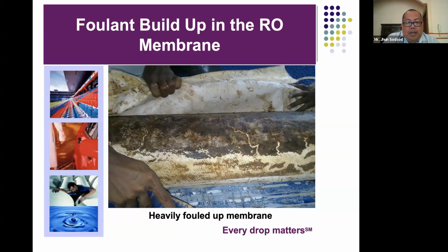So to make everything clear, I requested the in-charge of the RO process if we could take one membrane, cut it open, and see the real condition. We did, and this is what we found. The in-charge could not believe this much foulant had built up in the RO membranes, because according to them they have very good pre-treatment—feed water turbidity less than 1, SDI less than 3—so technically there should be no foulant. But despite that, we saw this.